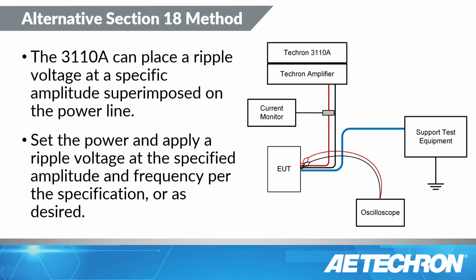And as a result, you're going to end up with two measurements. The current times the voltage does not need to exceed 100 watts. So if you're drawing a lot of current when you're trying to induce the voltage, there is a secondary standard or secondary limit that allows you to back off the voltage to avoid inducing excessive current.